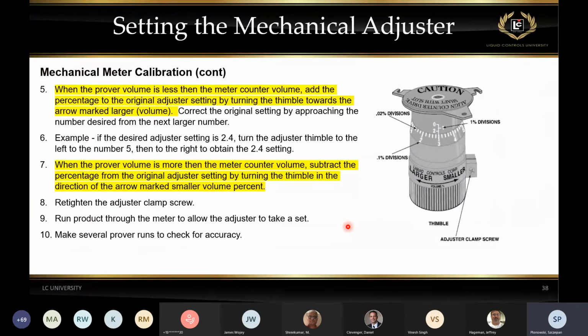If the prover volume, so volume delivered, is less than volume registered by the meter, we would add percentage error to the reading on the adjuster. Now, what is the adjuster reading? If you look at this adjuster here, and you see where those two scales are crossing, we're right at 2.3. That's our adjuster reading. If our percentage error, let's say, is 0.5%, we would take 2.5, and in this scenario, we would add to it. So 2.3 plus 0.5%, our adjuster reading would be 2.8. We would have to take the thimble and start turning down towards a setting that's 2.8.